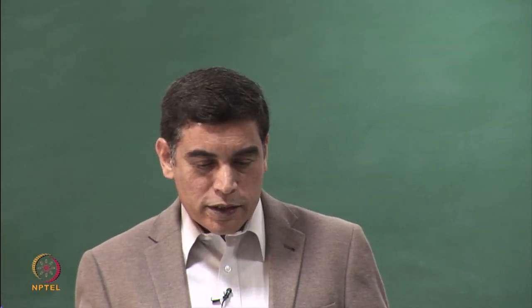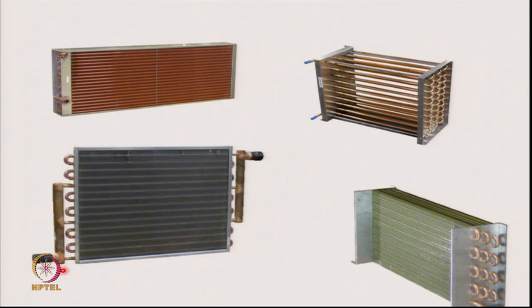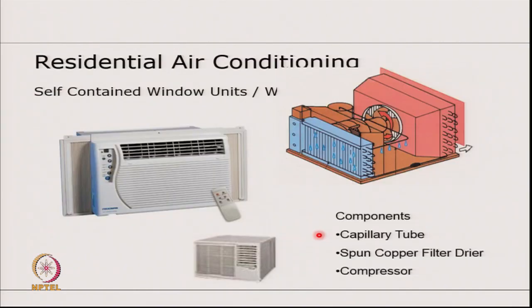Then we've looked at different coils before already. The one unique thing here is a coated condenser coil, and then a bare set of tube banks. So where there is no major enhancement required on the outside, then something like this can also be used. This and this would typically be parts of a window air conditioner, which is again a residential air conditioner, like this. And here the expansion device would be a capillary tube. Because of cost, it will be a low cost device.